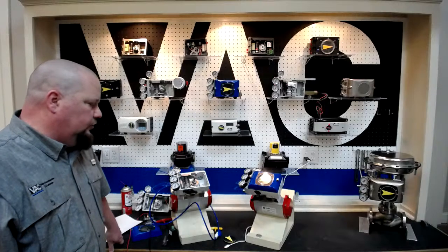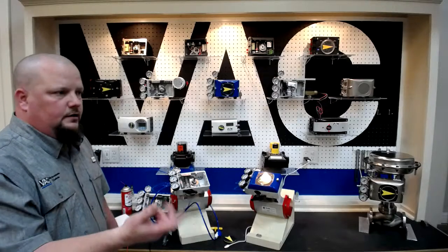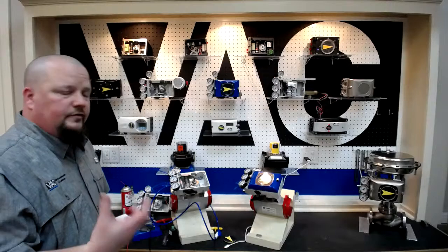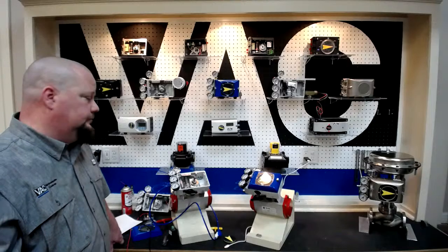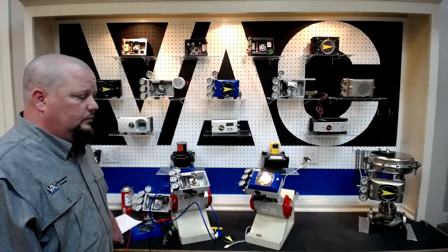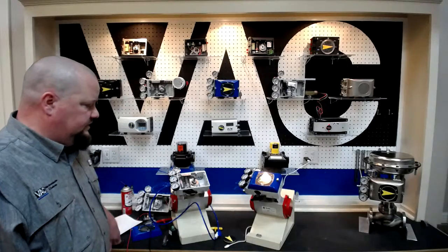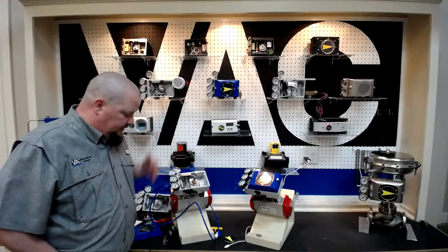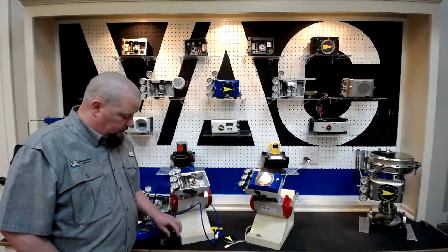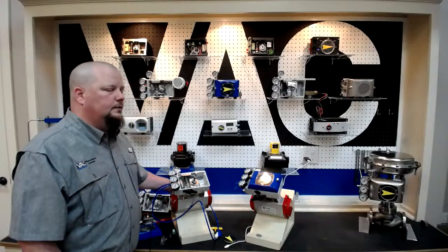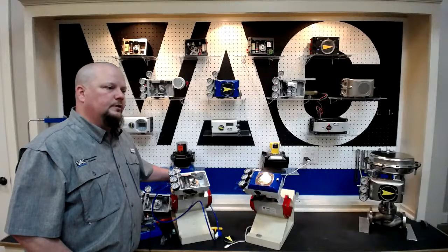But when we get these calls in from day to day, those are the things we get the calls on the most. Like Carly said, I'll reiterate that if you've got a lot of questions on this, and you may see things that we haven't seen yet, give us a call. We'll see what we can do to help you out, and we'll work through it. But like I said, the biggest things we see are setup issues with the cam, and then air quality issues that have damaged the IDP due to oil or moisture getting through it, and the same thing with a pilot. But luckily with a pilot, most times it can be cleaned, and we should be able to put it back in service without having to replace it.